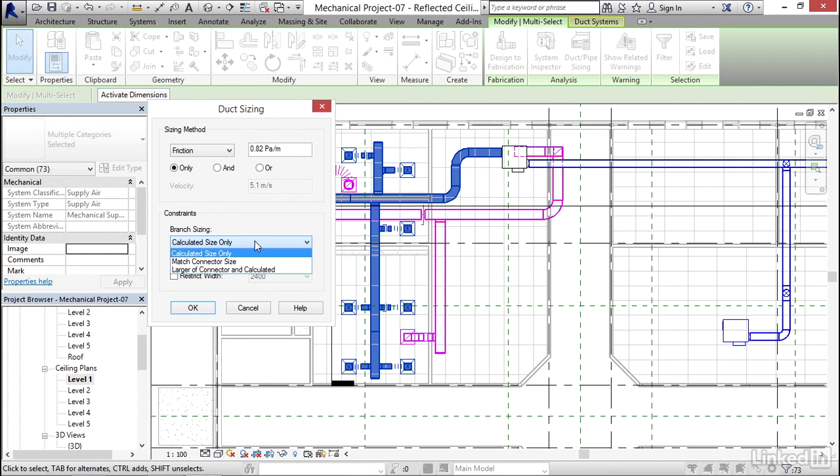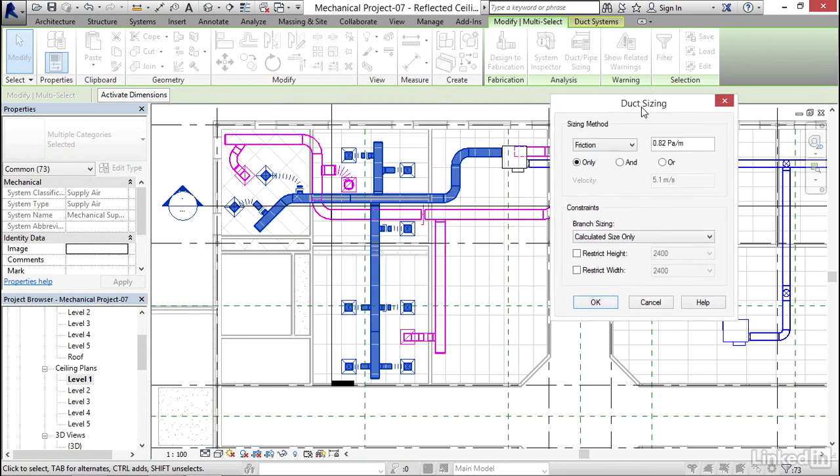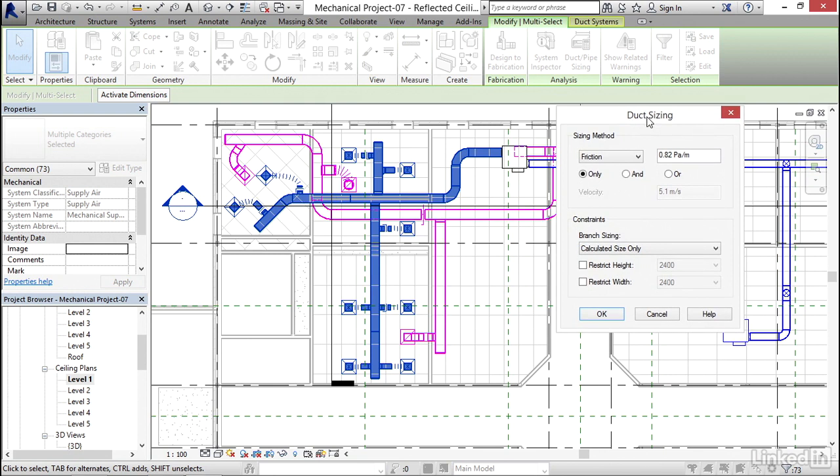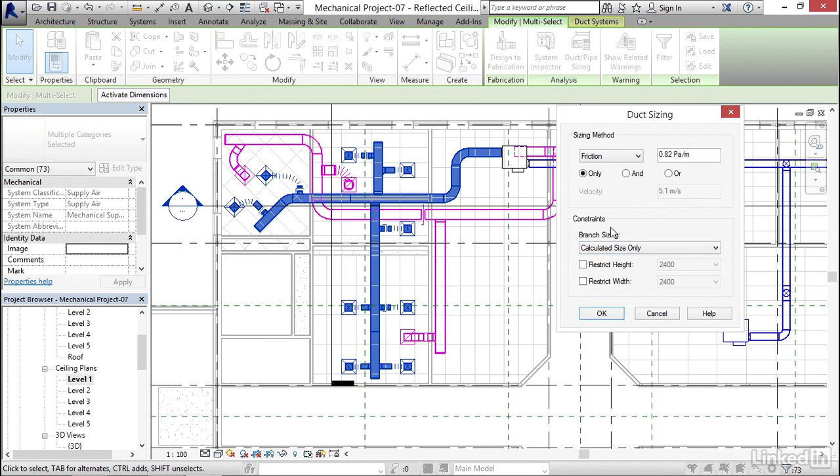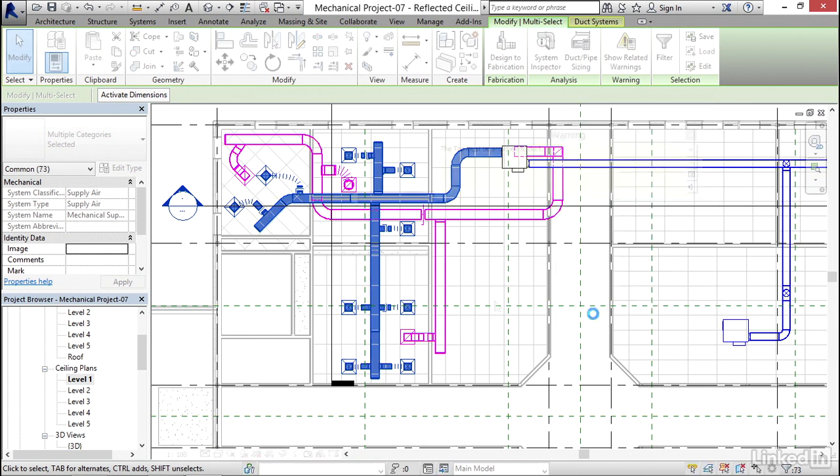I'm going to allow all of the rest of the defaults. Branch sizing, we can match connector size, or we can go to the larger of connector and calculated. Let's do calculated size only and see what happens. Because a lot of times, your fittings are going to blow up, and you have to just go back through and reconnect. You can try to avoid that, but generally it happens anyway. So constraints, my branch sizing, I'm going to keep calculated size only. Now I'm just going to hit OK.